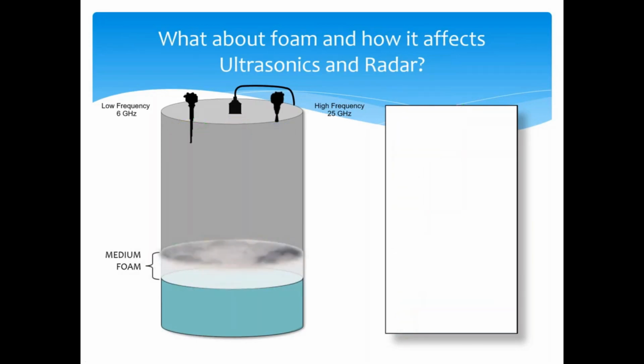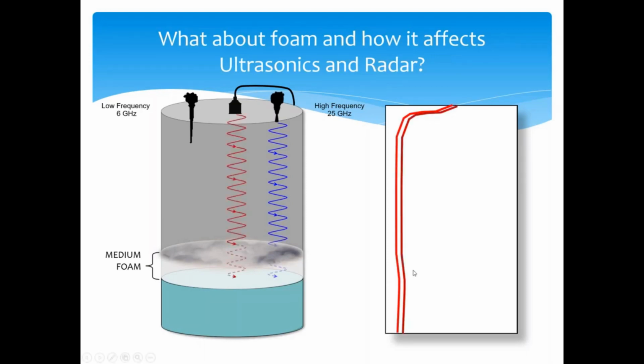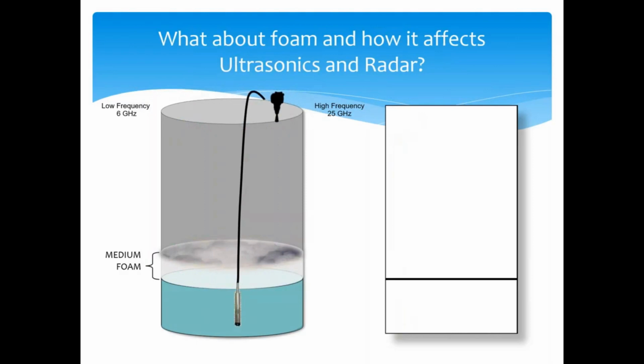Now where we really get into the head scratcher and we don't have a great non-contact answer is when we're dealing with medium foam. So I would describe medium foam more similar to like if you give your kids a bubble bath and you've got some airy foam bubbles in that bubble bath. If I do high frequency radar, I don't get a signal return. Ultrasonic, same thing, no discernible signal return. And low frequency radar, it's the same thing. There's no real signal return. So what would our answer be for something like this? This is ideal for a submersible pressure transducer or a contacting technology.